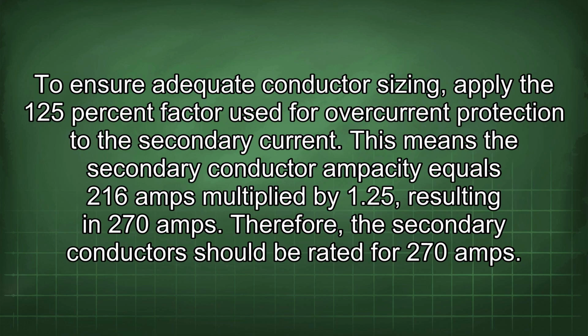To ensure adequate conductor sizing, apply the 125% factor used for overcurrent protection to the secondary current. This means the secondary conductor ampacity equals 216 amps multiplied by 1.25, resulting in 270 amps. Therefore, the secondary conductors should be rated for 270 amps.